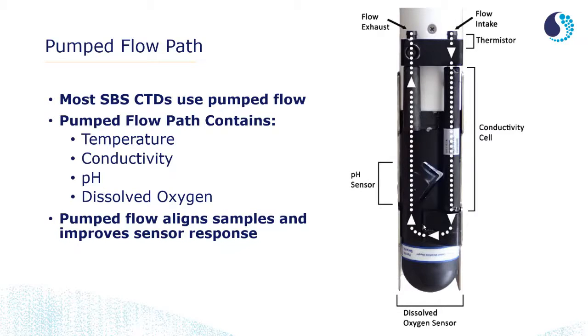So this U-shape really depends on the pump. It's pulling water into the intake, past these sensors, and then pushing the water out through the exhaust. If you're profiling with this, because it's shaped like a U, your water is not going to be able to enter very easily at all, especially with the anti-fouling guard in place. So you really need to use your pump with this instrument—it's designed to be used with a pump. What will probably happen if you disable the pump, which you can do by turning the minimum conductivity frequency up to 1,000,000 hertz or something—I don't recommend doing that—is you'll probably get seawater into your plumbing, and then all of the samples after that will effectively be that one parcel of water currently in the plumbing, because the pump isn't replacing it with new water. So do not use this for profiling applications. It's designed to be used for moored applications. That is my recommendation.